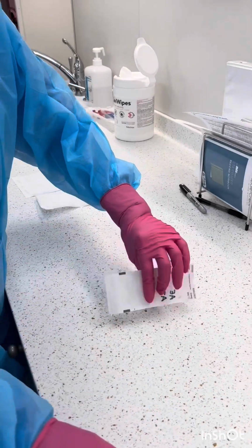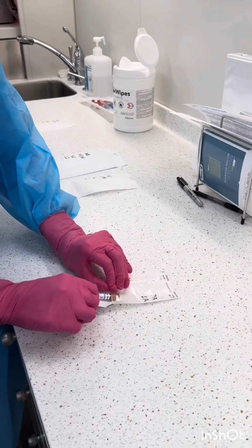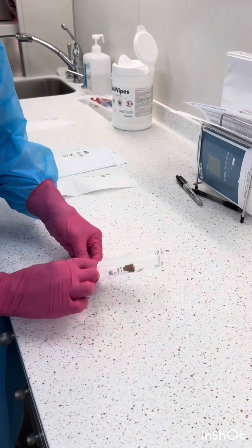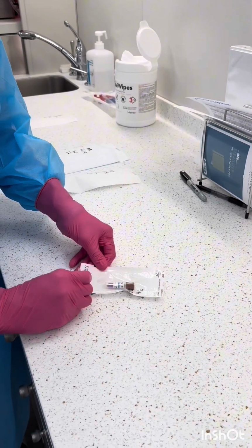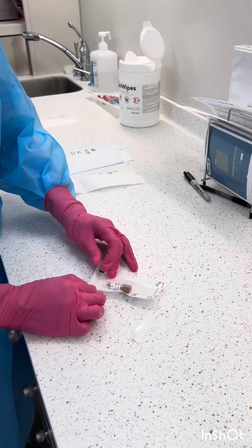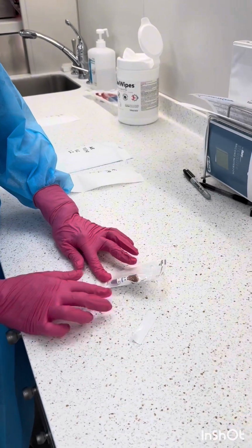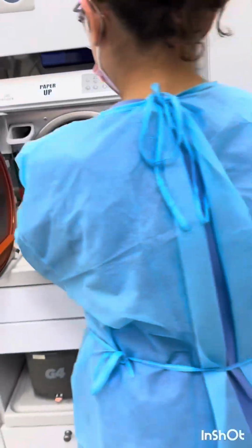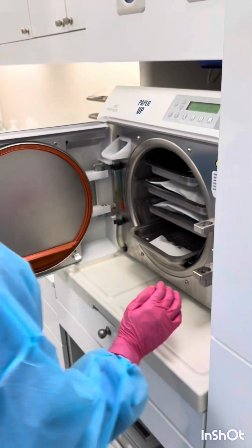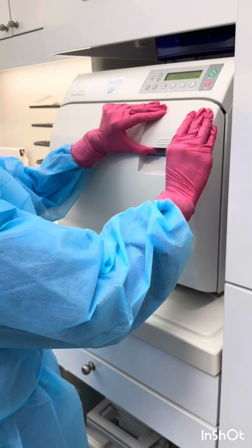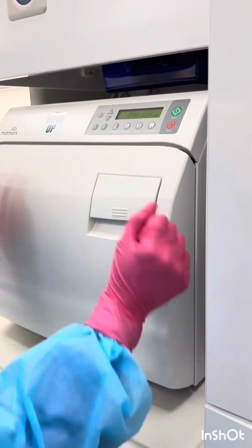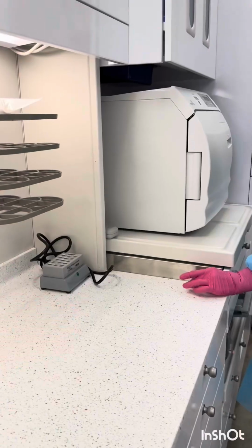Once a week, we want to complete the biological monitoring. To do this, place a vial inside a sterilization pouch and place it inside the autoclave and let it run on a normal cycle. We always want to leave another vial sitting out to use as our control group. To start the autoclave machine, we want to hit pouches and start.